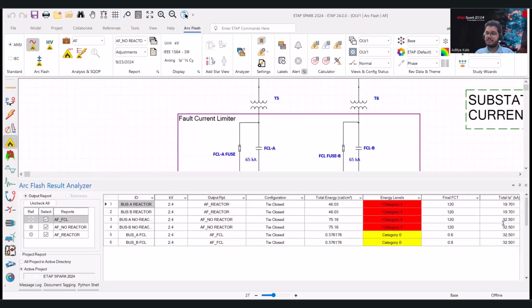the fault current remains the same, so it's the exact same as the case was with no reactors. But we have a very fast acting device here that acts in 0.6 of a cycle, which leads to very low incident energy. So let's look at the arc flash results.